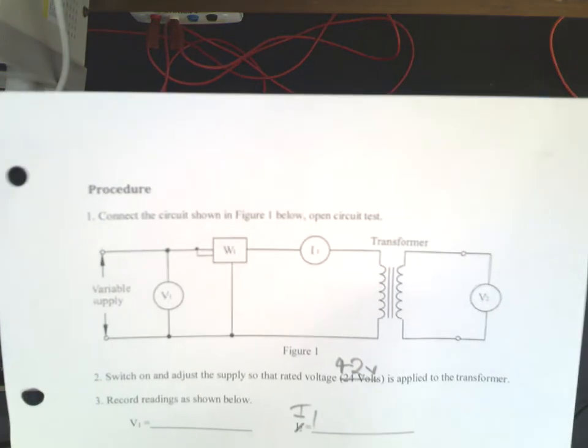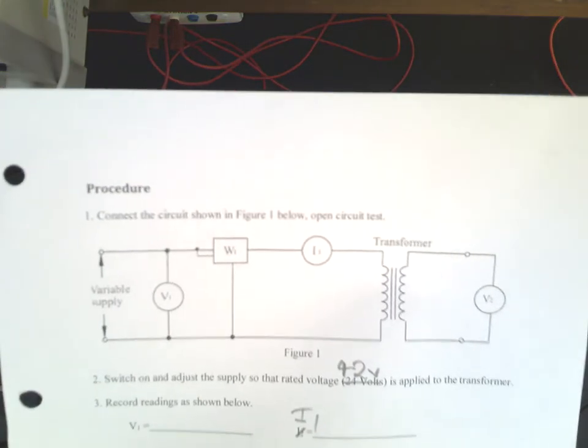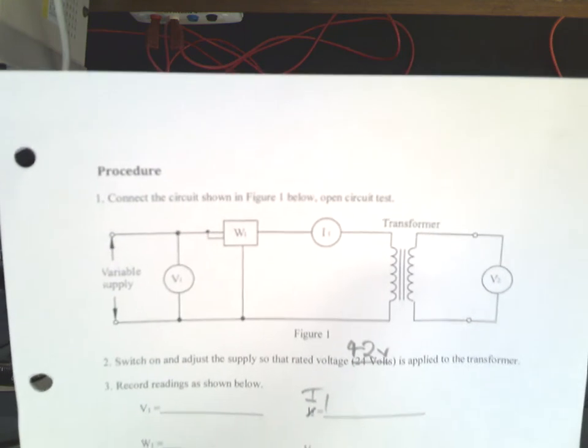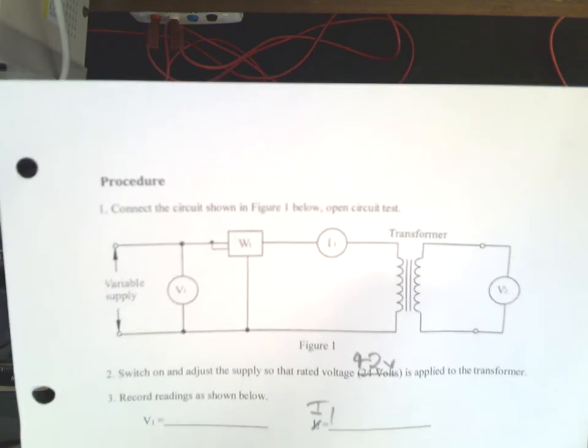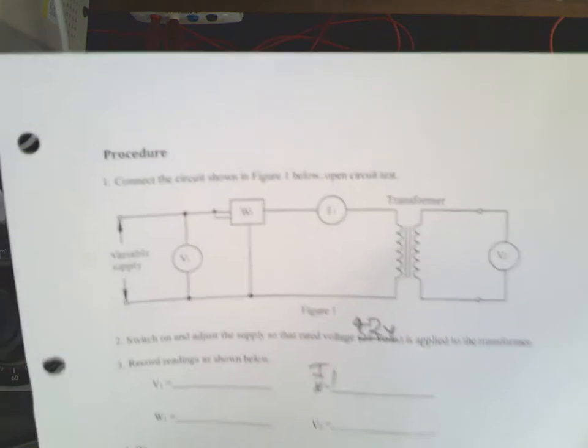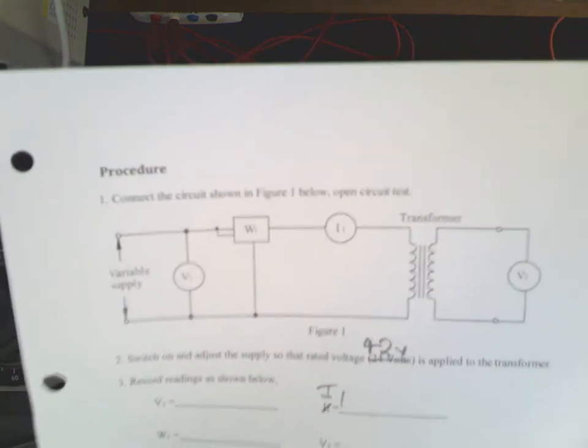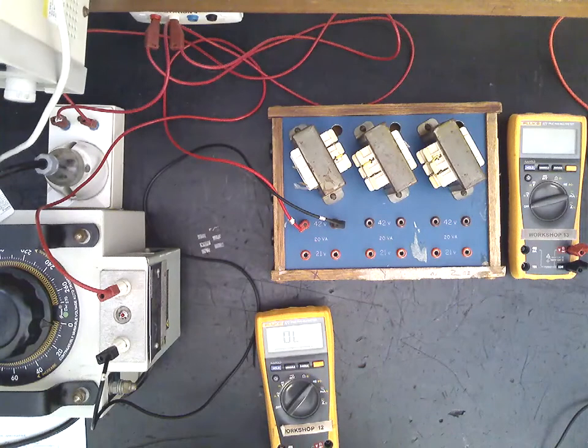There's our open circuit test for the transformer. So we've got a watt meter in the primary of the transformer, a volt meter across the supply, and an ammeter down here that's measuring the current for our iron loss test in the transformer.